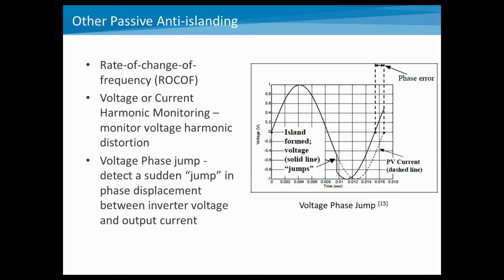Additional passive anti-islanding techniques include things like rate of change of frequency, looking at voltage or current harmonics, looking at things like a phase jump when all of a sudden an island is formed because you do typically have a load mismatch. You'll see that in the voltage or current outputs.